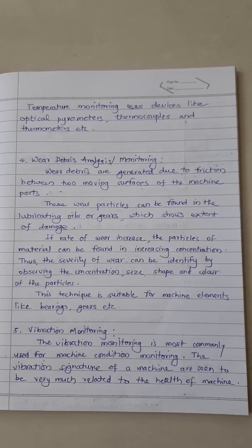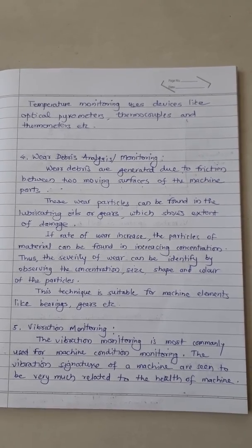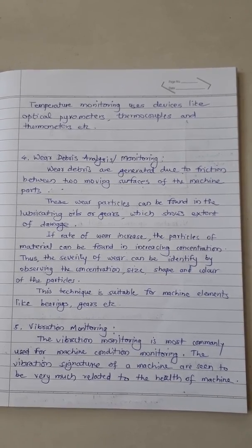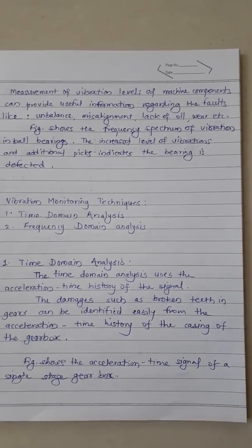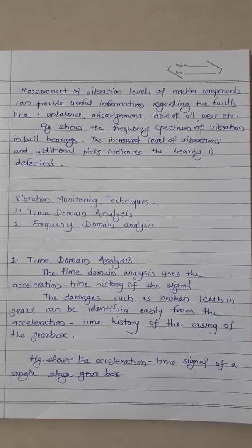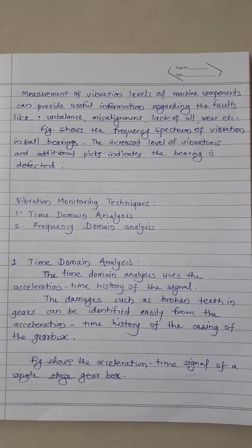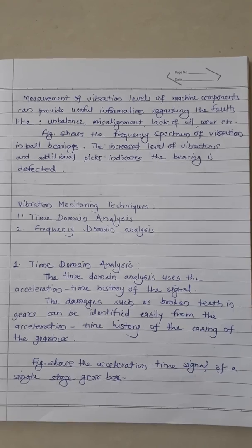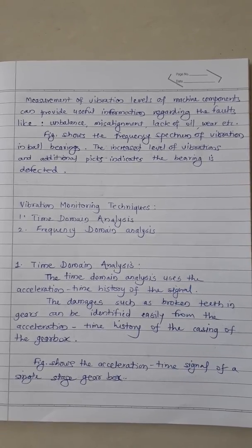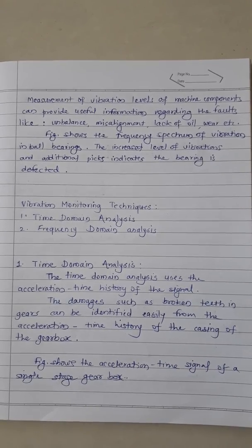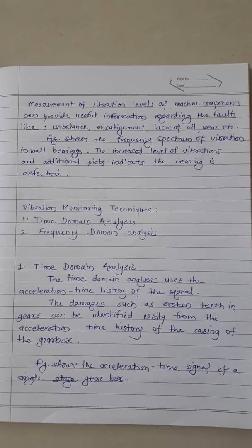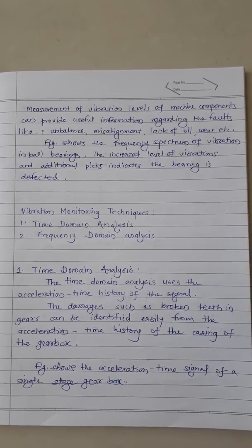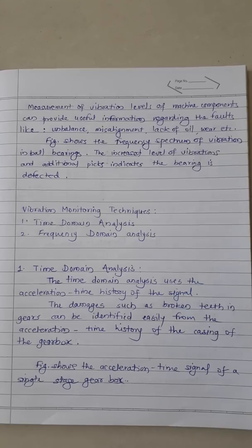Vibration monitoring is most commonly used for machine condition monitoring. The vibration signatures of the machine are seen to be very much related to the health of the machine. Measurement of vibration levels of machine components can provide useful information regarding faults like unbalance, misalignment, lack of oil, wear, etc. When vibration levels are measured, conditions like unbalance, misalignment, insufficient lubrication, and wear and tear can be identified. This information can be measured by vibration.